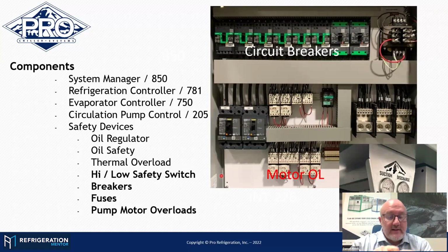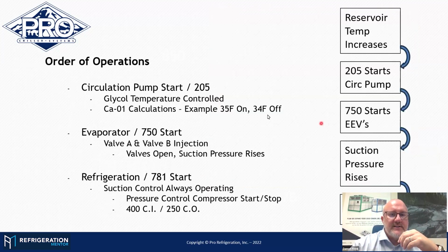So we've got our electronic refrigeration controls. We've identified those. We've identified our safeties. Now we're going to jump into the order of operations, which is really broken down at its simplest level. I think it's very common for us as mechanics to want to jump into the difficult side of things. Well, how's the high pressure valve being controlled? What's going on with my flash gas bypass valve? You need to be aware of that on the back end.